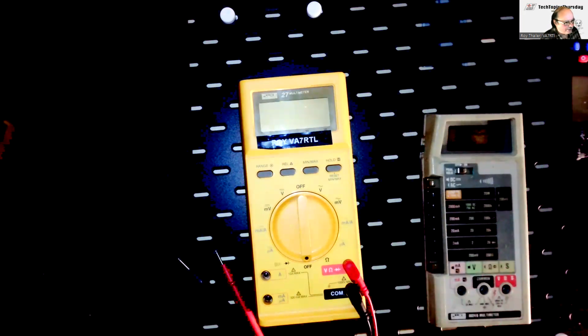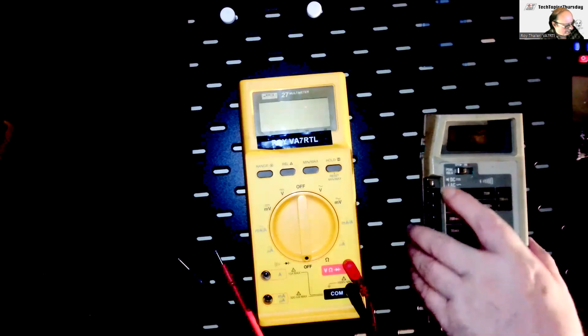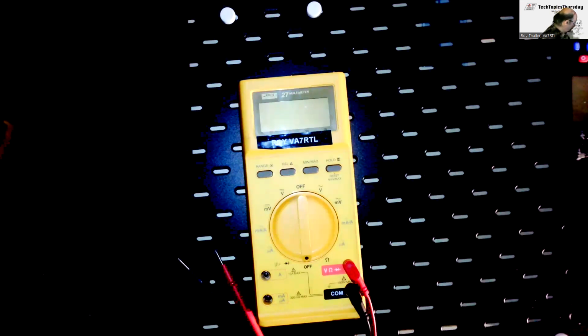If you're measuring low voltages and dealing with transmitters, pretty much any meter will be okay if it says category 3 on it. Even if you're doing a lot of measurement on electrical power, I would get something from a reputable manufacturer that says Cat 3 on it, just to be on the safe side.